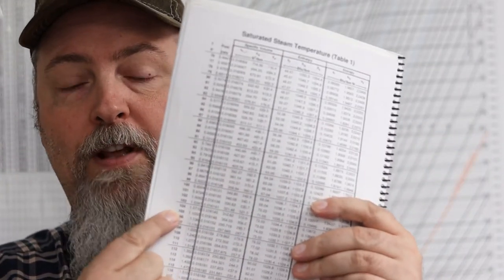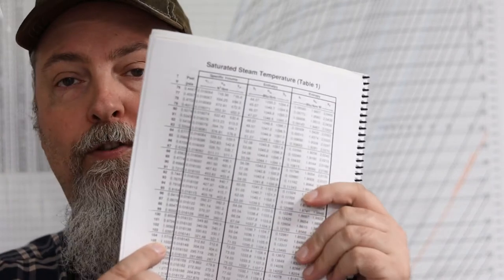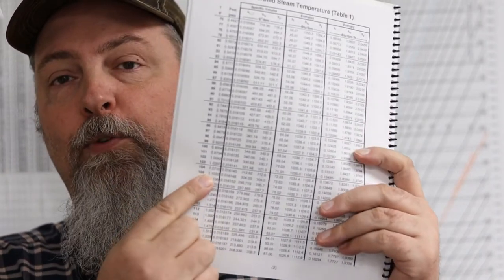For example, let's say you wanted to know what the saturation pressure was for water at, say, 105 degrees Fahrenheit. Well, you go find 105 degrees Fahrenheit on your steam table, under table one, and the pressure right next to it is your pressure of saturation. So saturation pressure is the pressure at which, for a temperature rise, the sensible heat stops and the latent heat starts, which means it's going to start converting to a vapor.